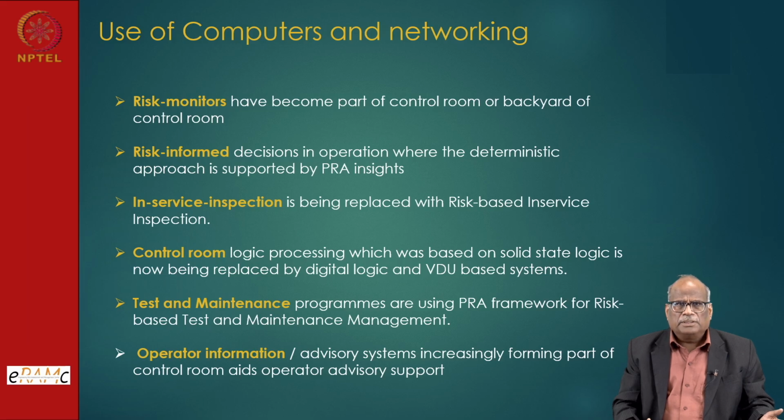Now, use of computers and networking, yes, the risk monitors are slowly becoming part of the control room or behind-the-control-room activity, wherever risk informed decision is a reasonably accepted model technology. In-service inspection was there earlier, and now it is called risk based in-service inspection, because PSA or PRA insights are available, and these are not only insights, models are used to structure the risk based inspection program.